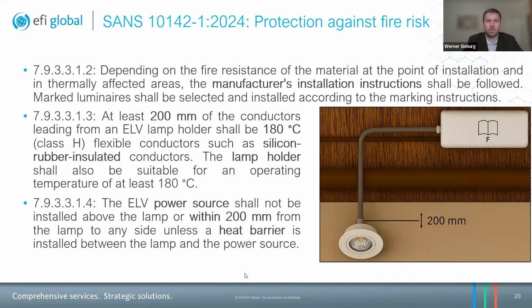Then the next subclause, sorry, not going to read all those numbers. At least 200 millimeters of the conductors leading from the ELV lamp to the holder shall be rated 180 degrees, which is class H flexible conductors, such as silicon rubber insulated conductors. So it's a high temperature insulator. The lamp holder shall also be suitable for an operating temperature of at least 180 degrees, just because of the fact that these lamps get quite hot.